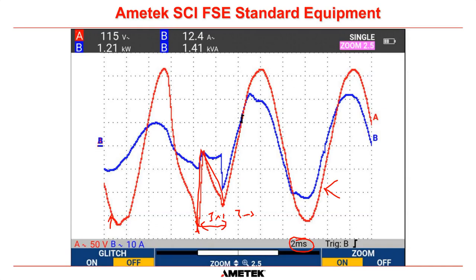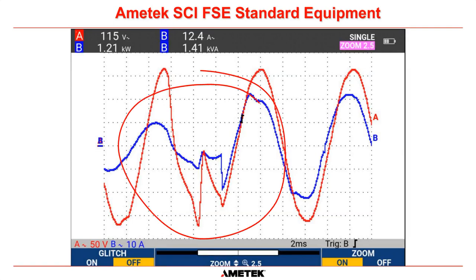And what we're doing is we're checking the spec of our UPS. Worst case scenario, you will see a 4 millisecond dead space between transferring from inverter to bypass. And pretty much a 4 millisecond dead space will not cause any of your load circuits to drop. This notch here would not have caused any issues on your load circuits in 99% of circumstances. So that's a good example of seeing exactly what's going on in the static switch at the transfer point. Very, very good information to have.